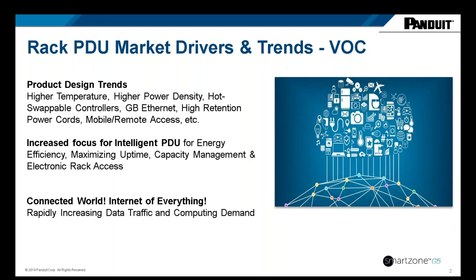And then of course, we touched upon the number one reason for equipment downtime. It turned out, especially in the Americas, it wasn't power outages or even surge spikes - we've got pretty stable power generally speaking. It was accidental disconnects of equipment cords - these are the C19s, C20, C13, C14 cords that go from the power distribution unit in the rack to the IT equipment, which was accidentally becoming disconnected.